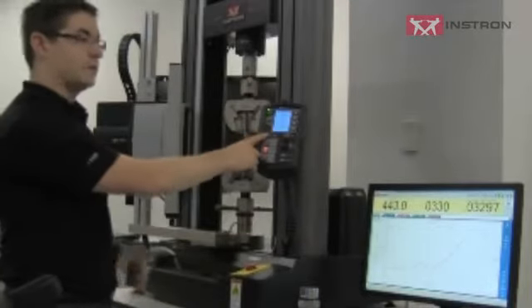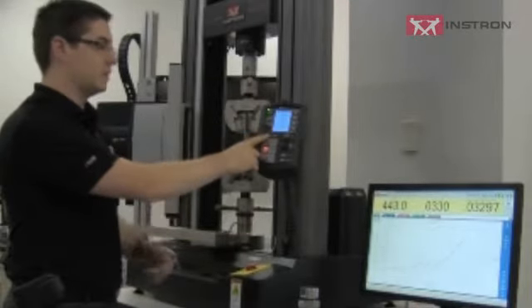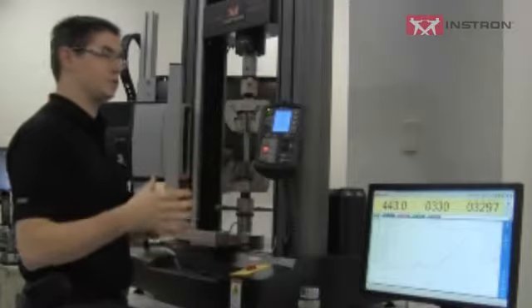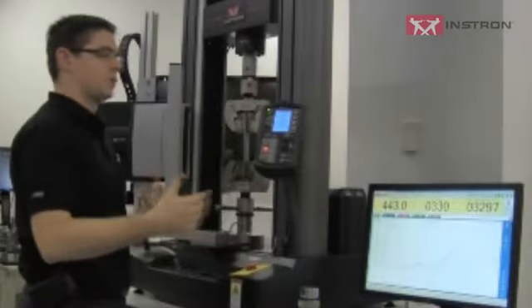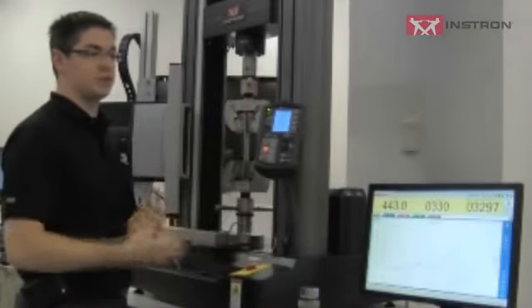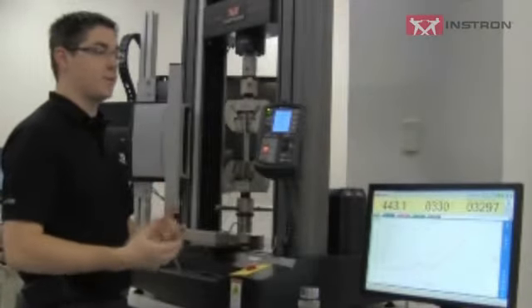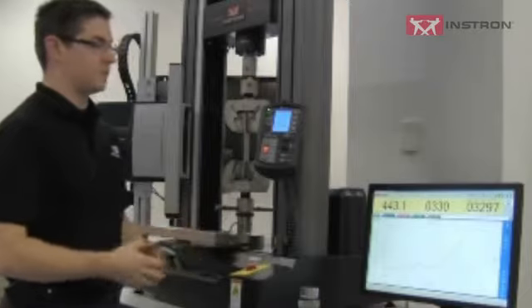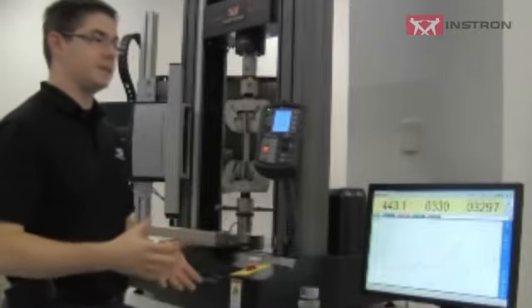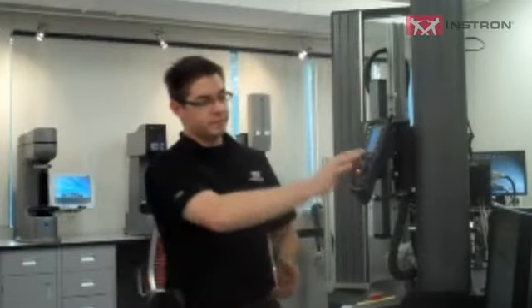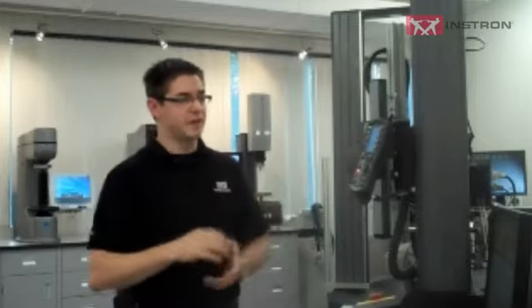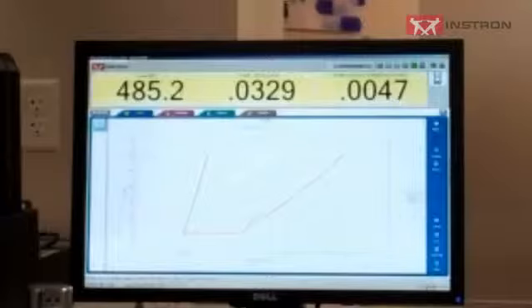Now I'm going to enable specimen protect. This feature allows the crosshead to reduce the stress on the specimen automatically. In this case, I've told it to stay within plus or minus 10 pounds. So it'll go from 500 down to, in this case, 7 or 8. It's still active.